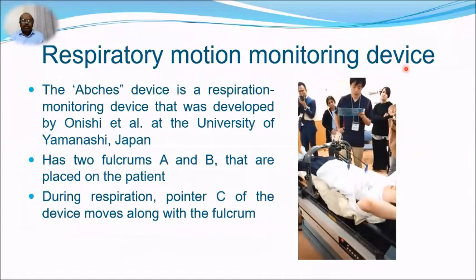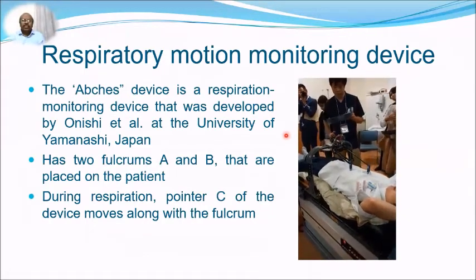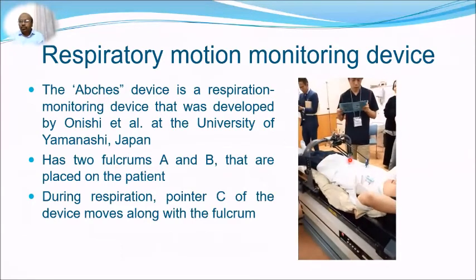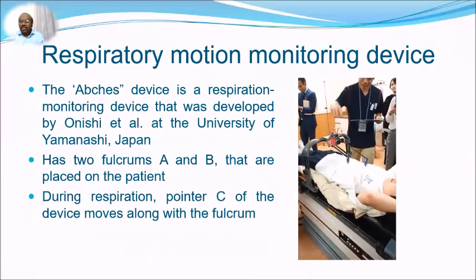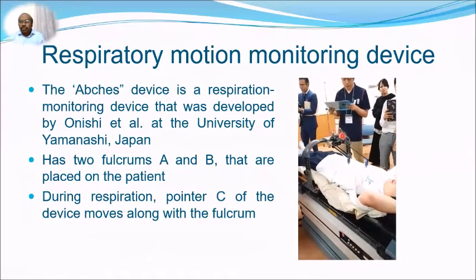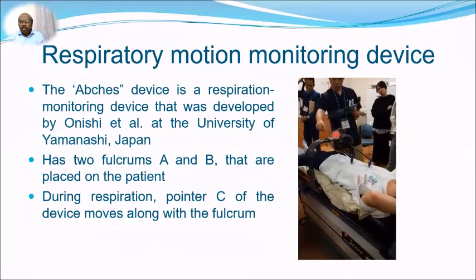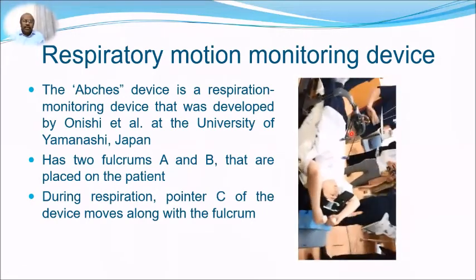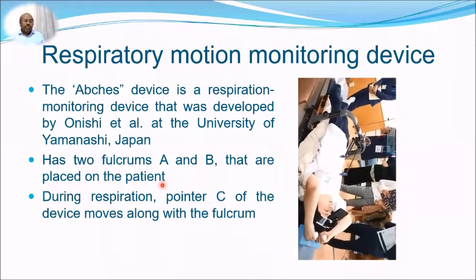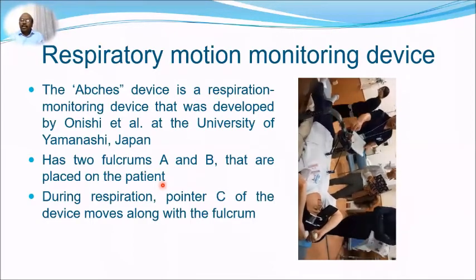One respiratory motion monitoring device is the ABCHES device from Japan. It has two fulcrums (A and B) attached to a pointer (C) that moves in different directions depending on the breathing motion. When the patient holds their breath, the pointer stops and a clip is placed at that position, monitored via video camera from the control room. This system is not interfaced directly with the linear accelerator, so treatment must be stopped manually, though a newer version interfaces with the linac automatically.